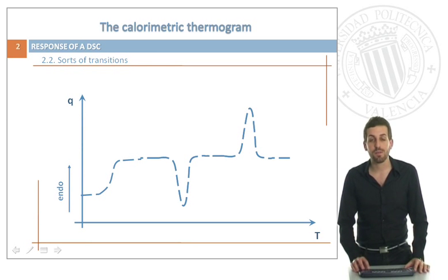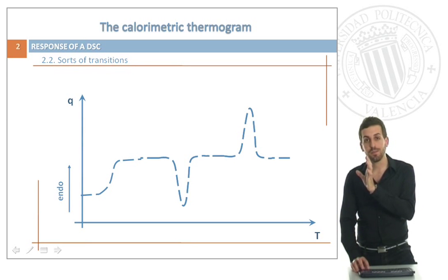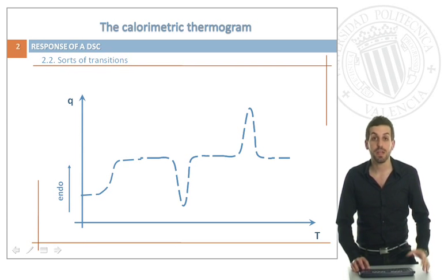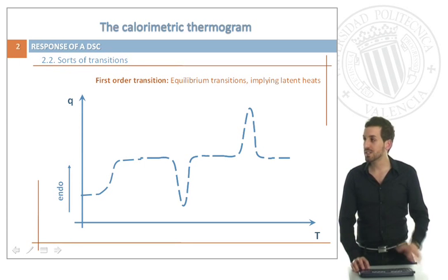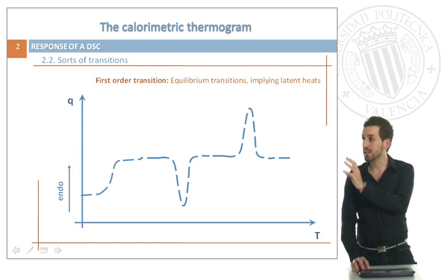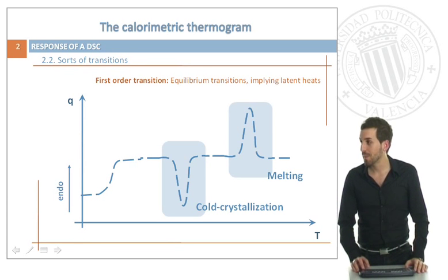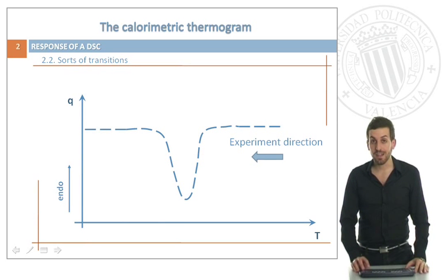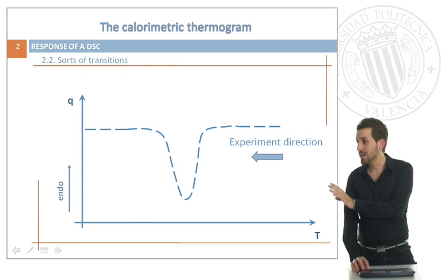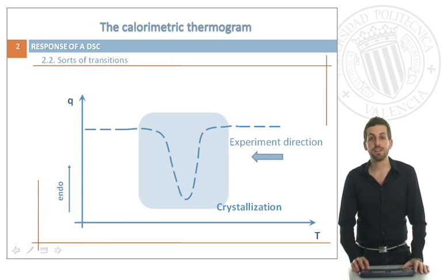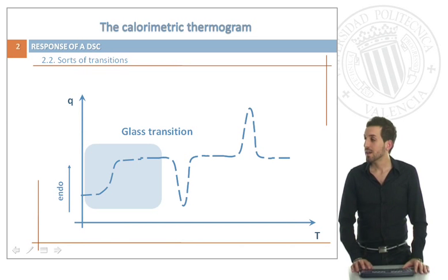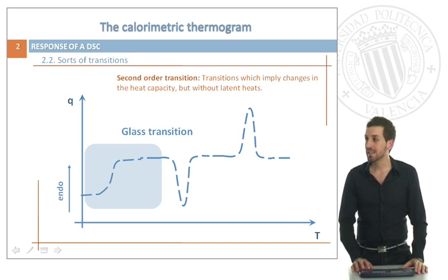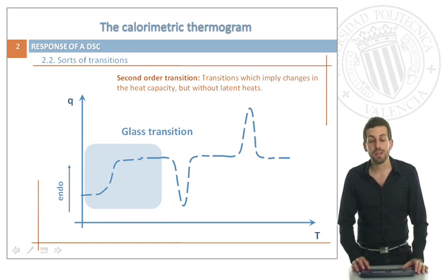Let's start with the response of our DSC. We have chosen a thermoplastic polymer because it will give us the most information. First, we will see the first-order transitions, which are equilibrium transitions in which latent heats are implied. For example, in the heating scan we can see cold crystallization and melting. In the cooling scan, the experiment direction goes from higher to lower temperatures and we can see the crystallization. Regarding the increase in heat capacity, this is a second-order transition and does not imply latent heat — only variations in heat capacity. In that case, it is the glass transition that we are seeing.